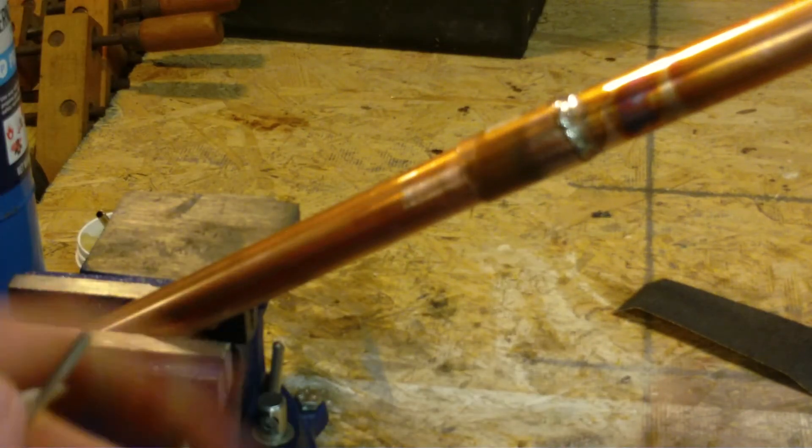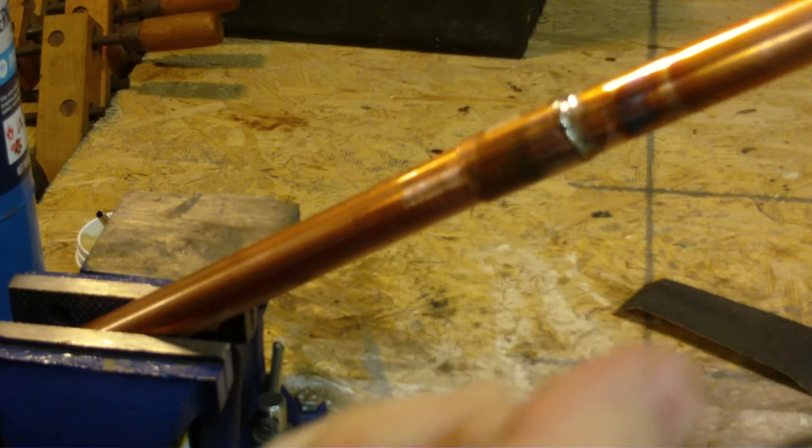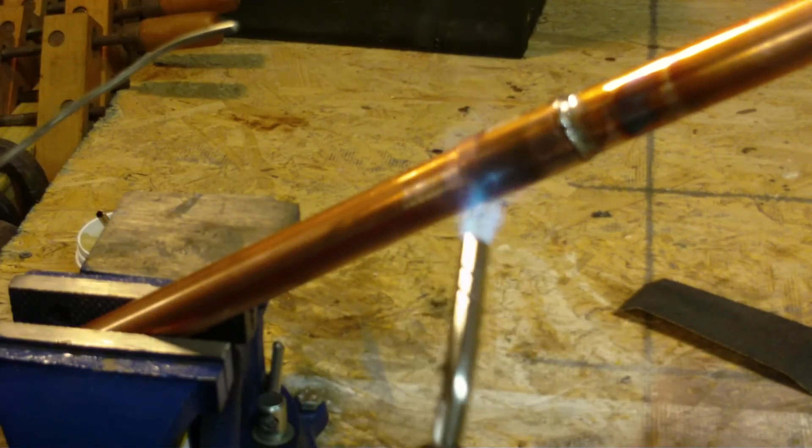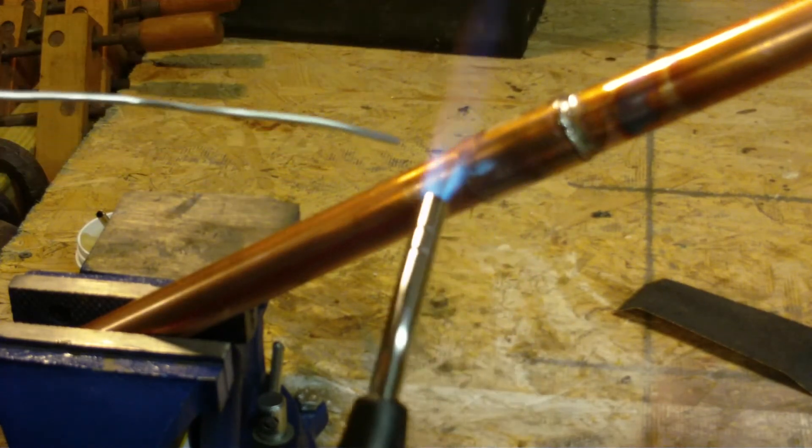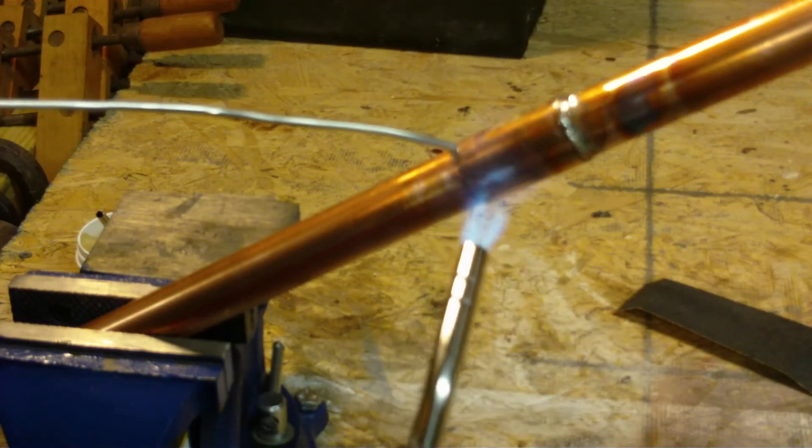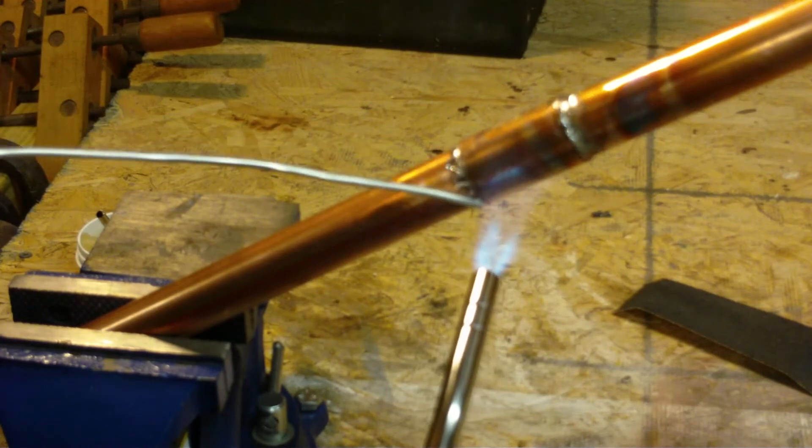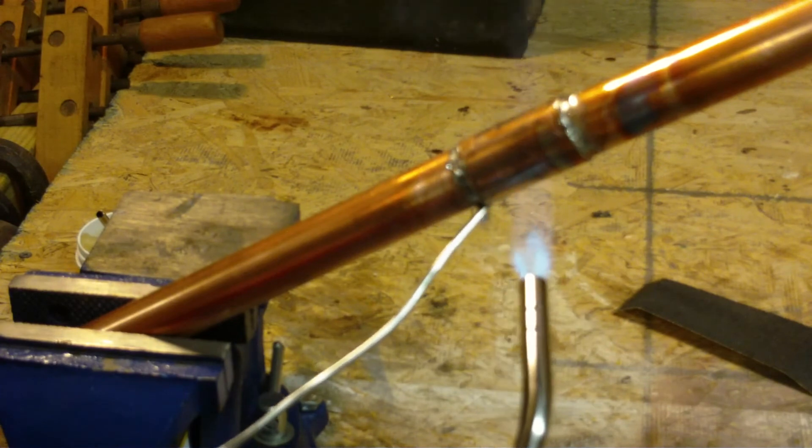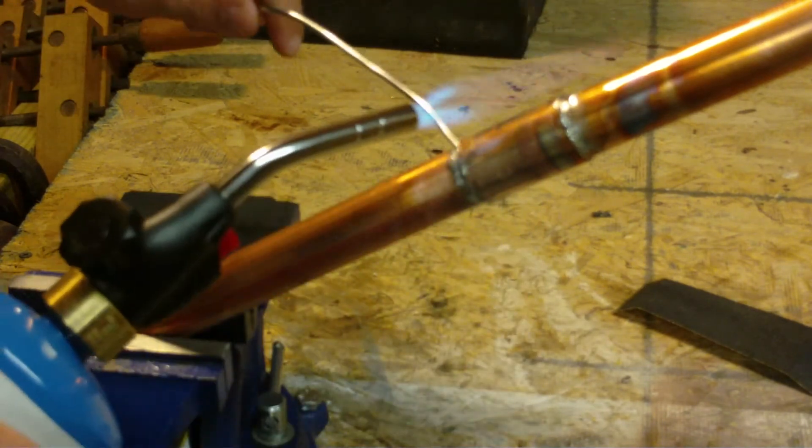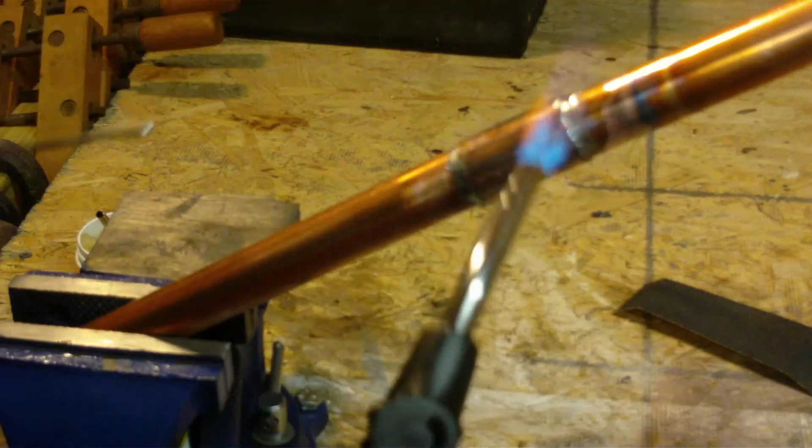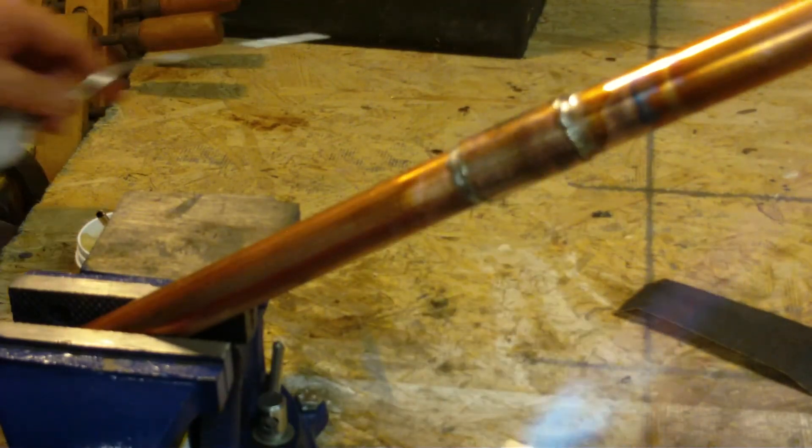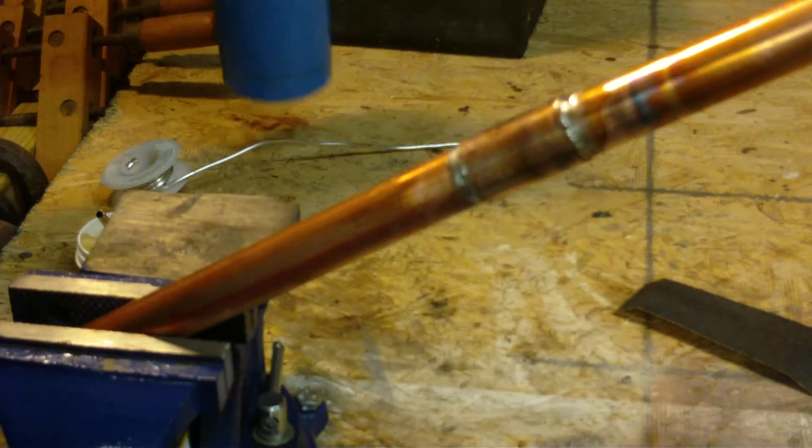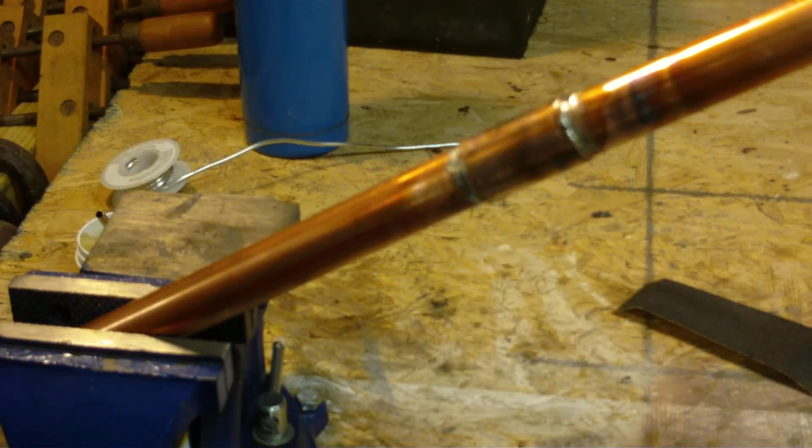I'm going to add some more solder to see the bottom of that joint. I'm going to heat that back up. When you start seeing the flux bubble inside the coupling, it's usually a good sign you're at the right temperature. Make sure you get all around there so there's no holes. And that's how you sweat on a copper fitting.